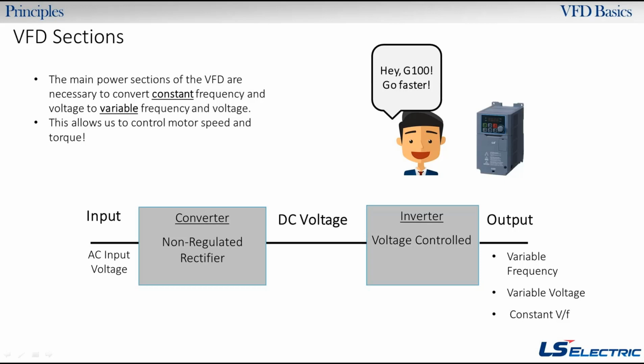Okay, so why we have these three main power sections is because we're converting a constant frequency and voltage over to a variable frequency and voltage, okay? And the whole purpose of that is because it allows us to control motor speed and torque. So if you think of a contactor, you're connecting 60 hertz, let's say 480 volts, across the line straight to the motor. So when you close that contactor, the motor runs up to full speed within a fraction of a second. There is no soft starting, there is no accel or decel time you could set on a contactor.